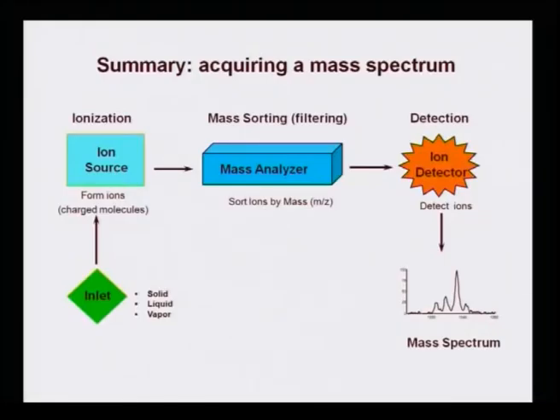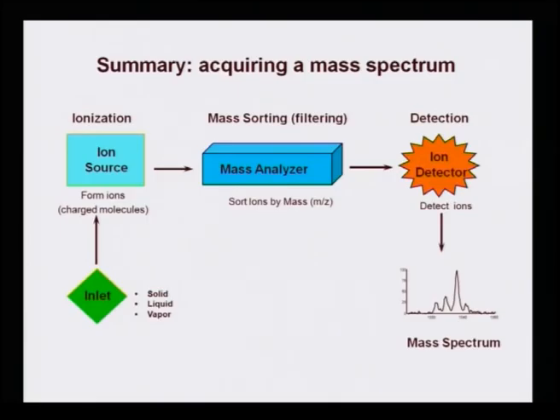To summarize the mass spectrometer workflow: there must be an inlet, which can accept vapor phase, liquid, or solid samples. Once injected, the sample goes into the ion source chamber where it is ionized using hard or soft methods. The resulting charged ions are sorted by m/z ratio in the mass analyzer and sent to the detector, where they are detected and amplified into a mass spectrum as data.